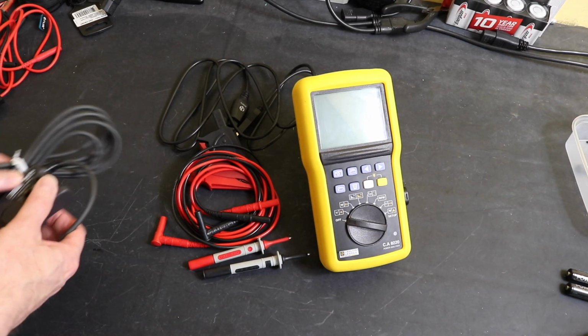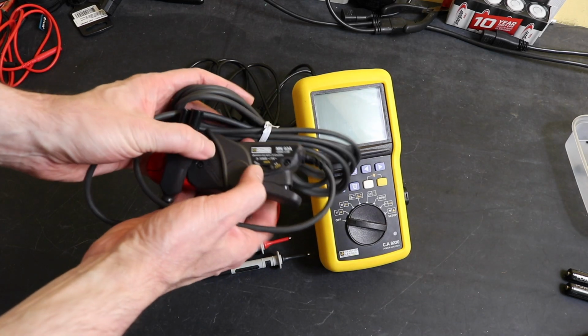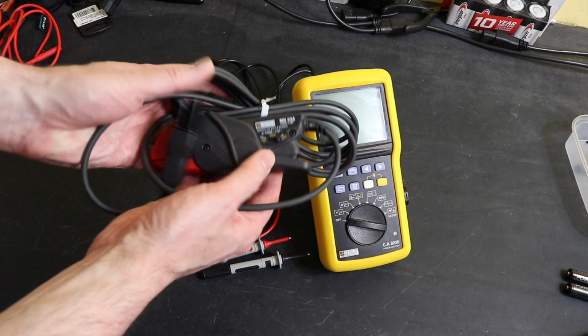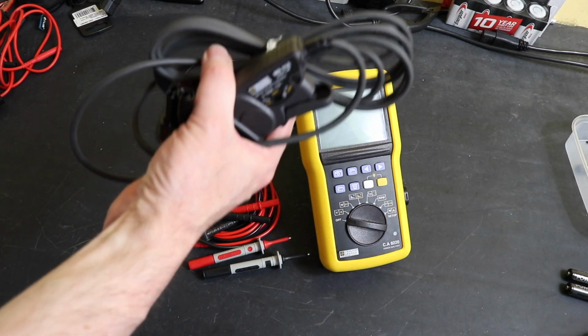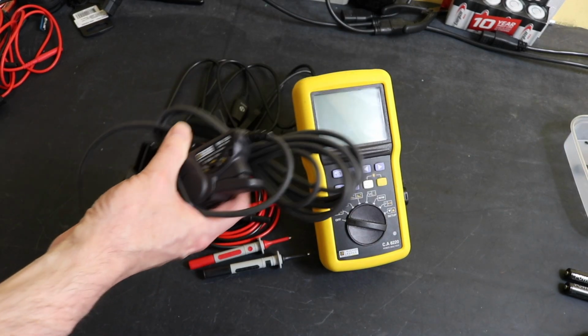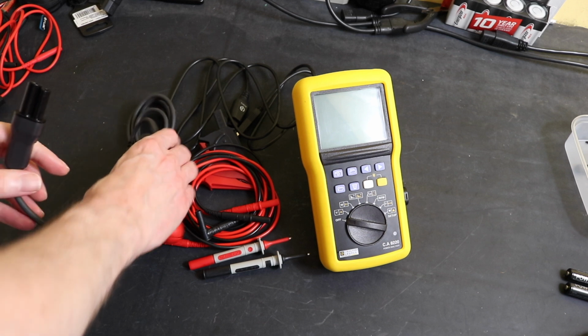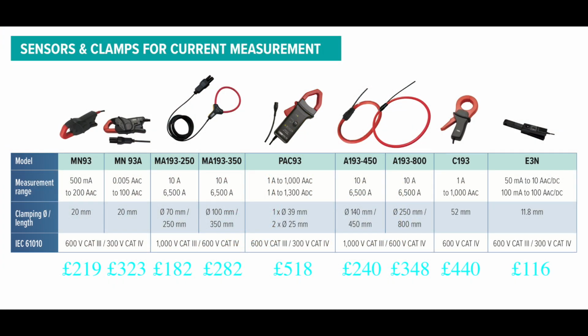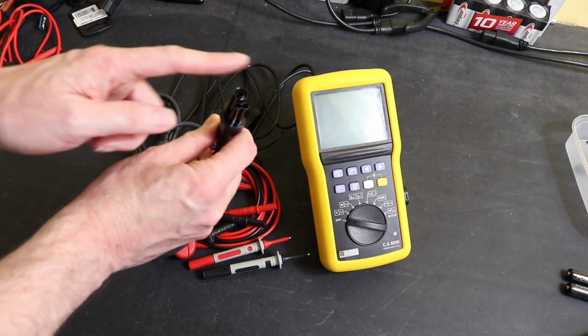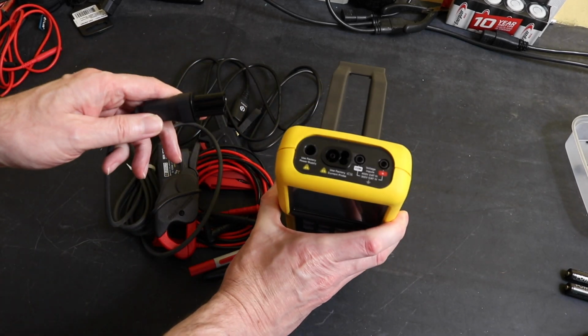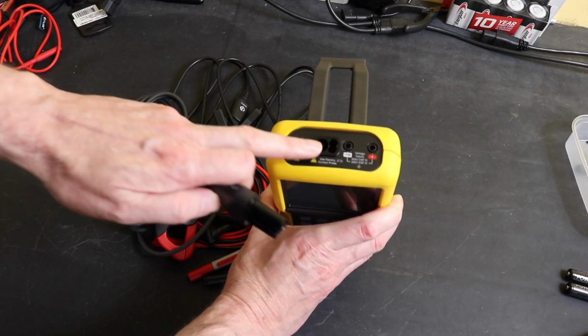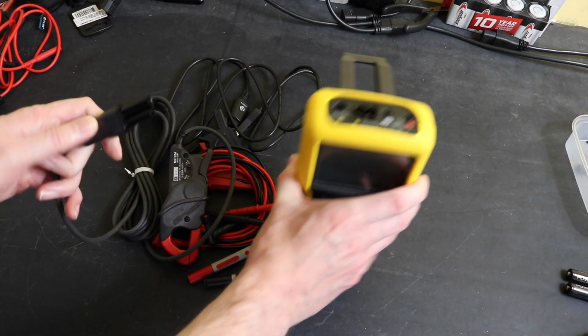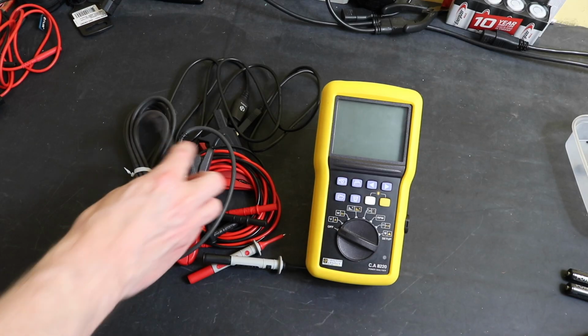So the one that came with mine is the MN93A. This is an adjustable 100 amp and 5 amp rating instrument, and on test meter that was £322. Now other clamps are available, so this may not be the cheapest clamp. There may be other ones out there, and there are obviously clamps with a higher current rating. However, I believe you are stuck with using a current clamp from Chauvin Arnoux because of this connector here that goes into the top of the instrument. This isn't compatible with another manufacturer with standard 4mm jacks, so you are stuck to using a clamp from Chauvin Arnoux.